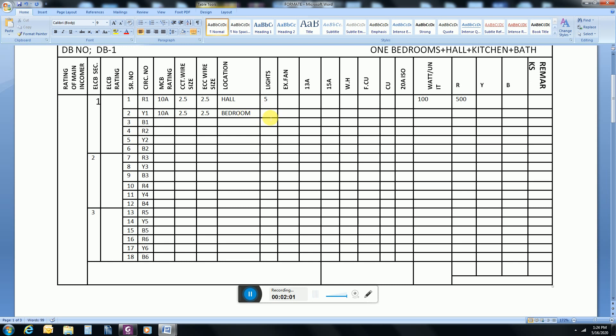For the bedroom, four lights are enough. Each light is 100 watt, so the total load on the yellow phase will be 400 watts. The MCB rating is again 10 ampere, wire size 2.5mm and ECC 2.5mm.